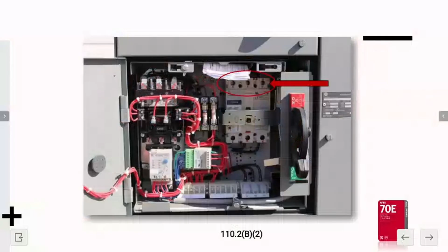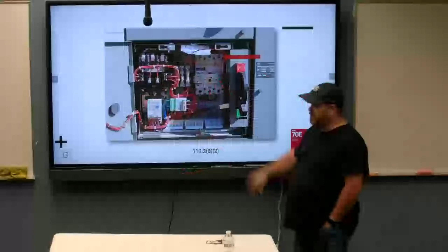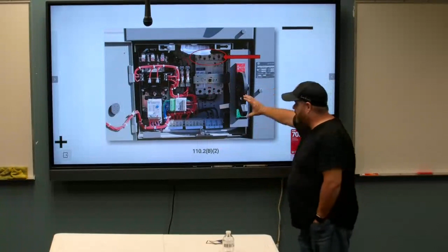So here's some examples of exposed. You can see this is an MCC bucket. They turned it off. Let's even say they put a lock and a tag on it. Are you still exposed to any live energy parts in this bucket? Absolutely. All you got to do is look at this arrow, right? The line side of the breaker is still attached to the main bus on that gear. So if the main for that whole bank is still turned on, you're still exposed. Once you get a tool out, a screwdriver, you're probably going to be tempted to make an adjustment if you see something loose, and bam, there's an arc flash. You're exposed, even with it turned off. That's why I tell people to take a few steps back, a couple deep breaths, and ask yourself, what am I exposed to? Now that I've turned it off and locked it out, what could go wrong?